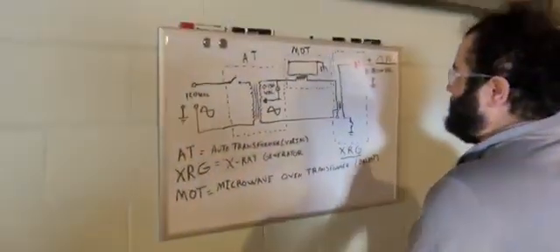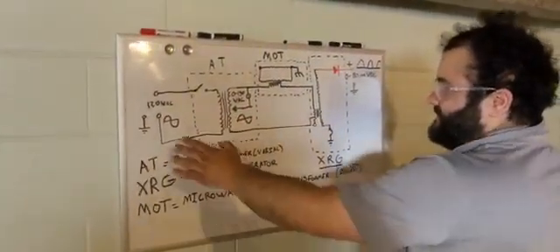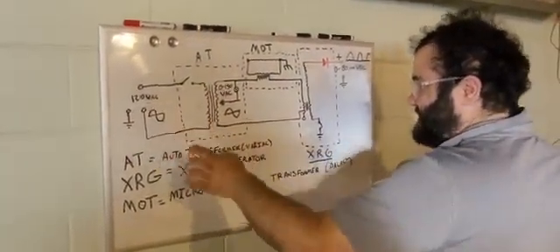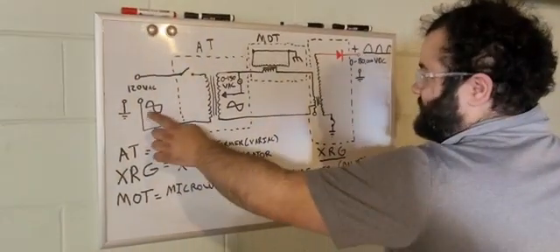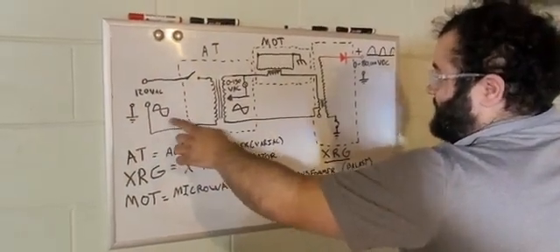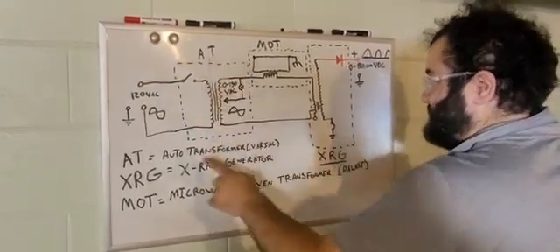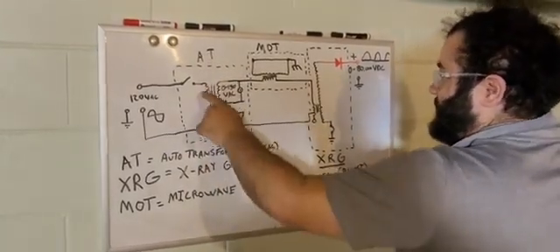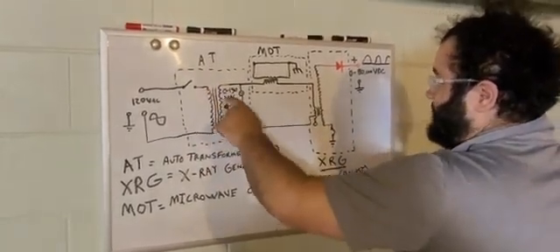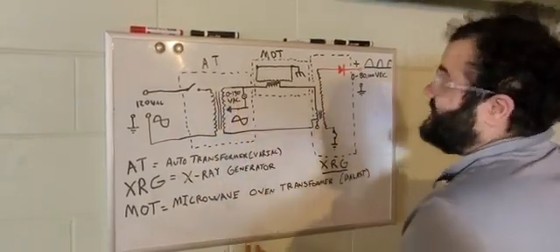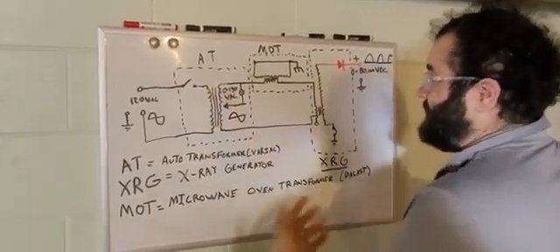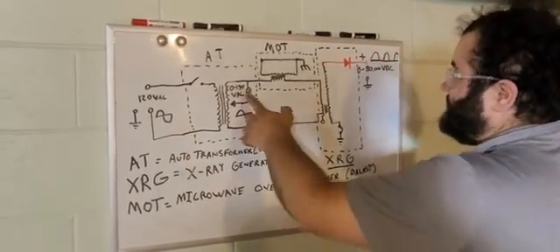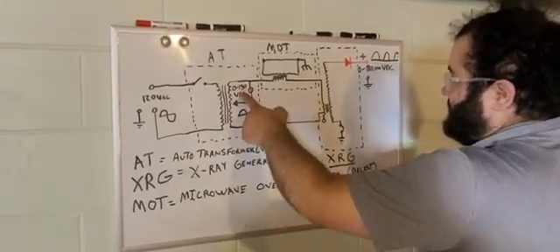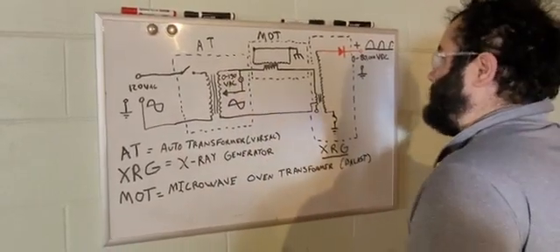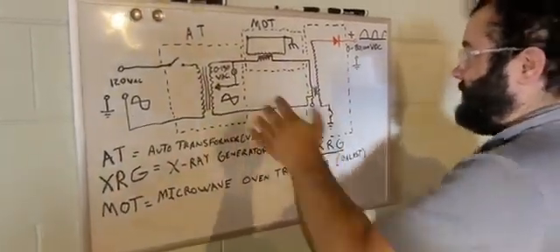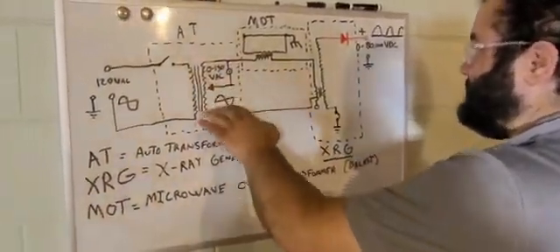Over here, this is the circuit we're looking at. This is the input from the wall, the 120 volts AC, because we are in the US, 60 hertz of course. AC sine wave coming in. This is the auto transformer, also known as a variac, and has a variable secondary that can go from 0. But in this case, it's not 0, it's 0.6 because there is some residual voltage in the transformer. And it can go all the way to 130 volts. Today, we'll probably only bring it up to 100, but its capabilities do go to 130.